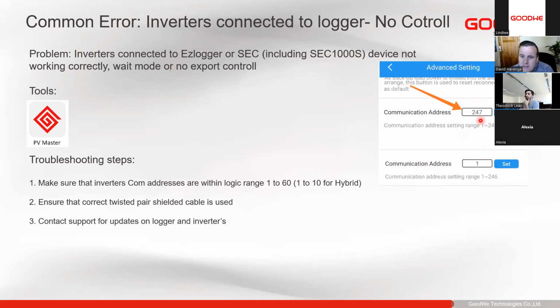As you'll see on the hybrids, we'll also have this setting. So we always need to set it in range. The hybrid range is 1 to 10. The on-grid range is 1 to 60, because our hybrid SEC1000S can only take up to 10 inverters, and the on-grid can take up to 60. So always remember to change that communication address from 1. So your first inverter will be number 1, second number 2, and so forth.